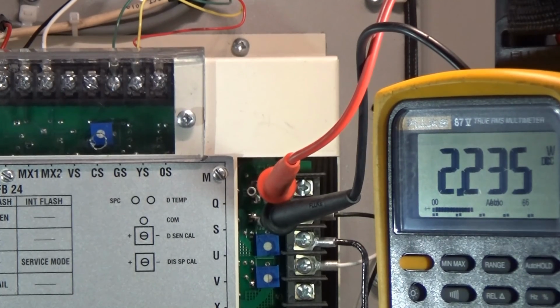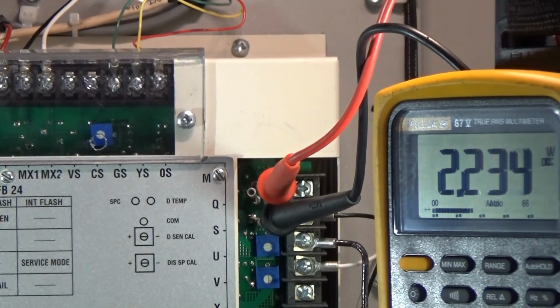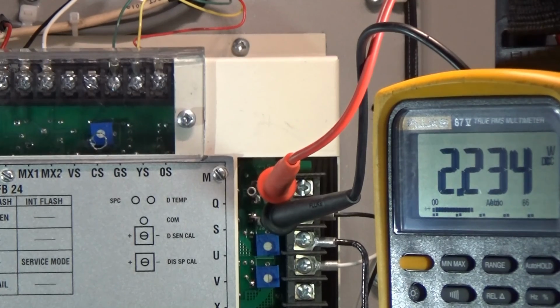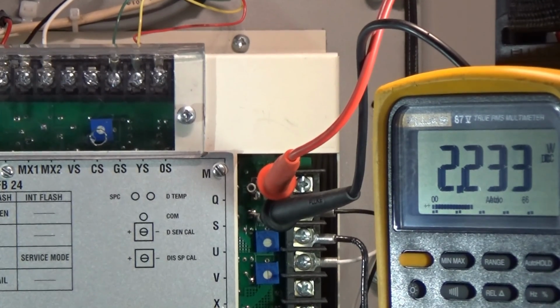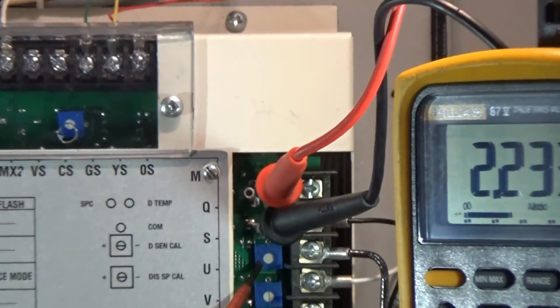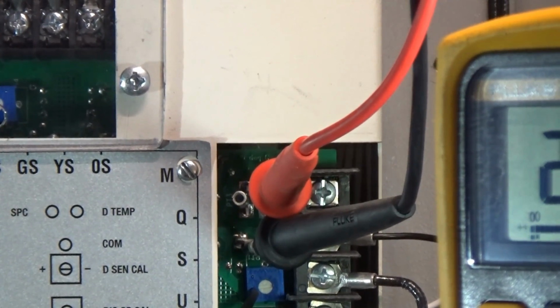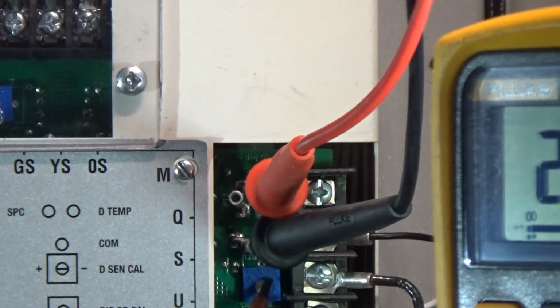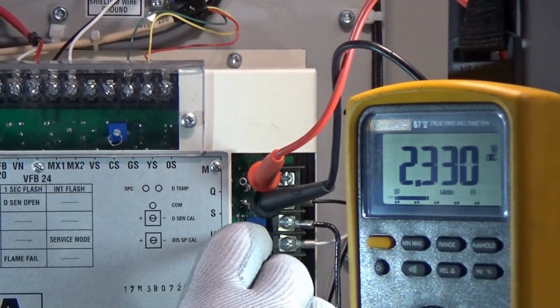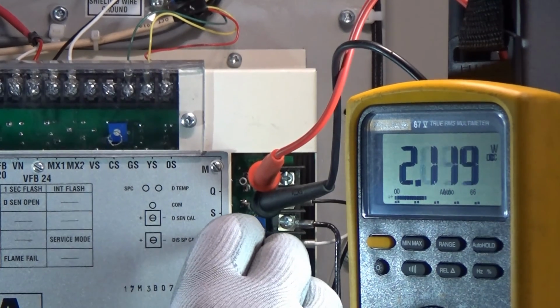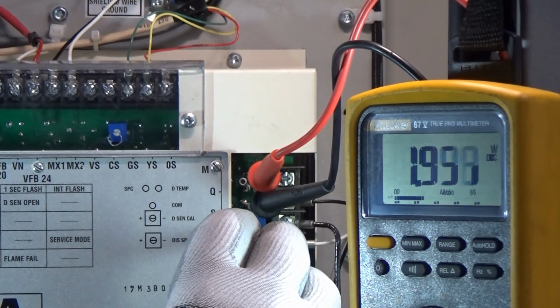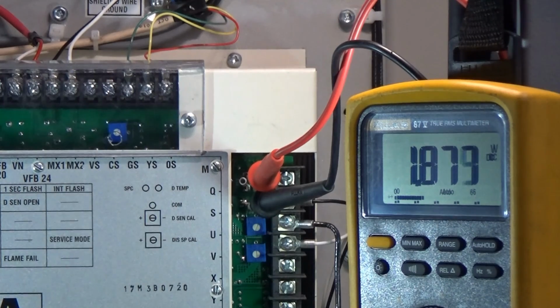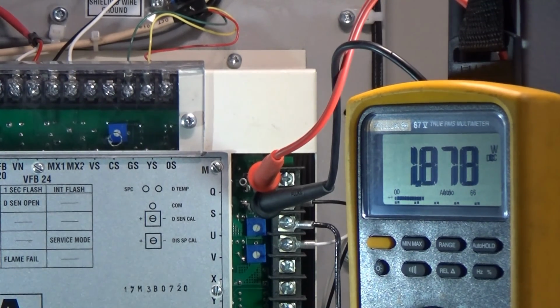Once your readings do not match, you will have to calibrate the discharge air sensor. To calibrate the discharge air sensor, the first blue pot below the test pin common is your discharge sensor calibration pot. Again, all you have to do is adjust this pot slowly till the meter reads what your thermocouple was reading. In this case, 18 degrees. Now your sensor is calibrated.